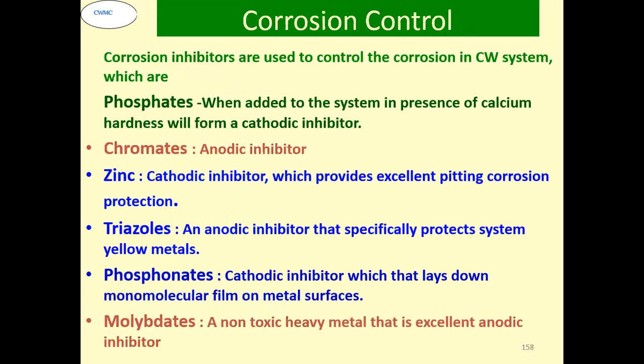Some of the important things are phosphates, chromates, zinc, triazole, phosphonates, molybdates. After that, chromates are generally ruled out these days because of the environmental considerations, and they are supposed to be toxic in nature, especially chromium 6+. Zinc is again a very good cathodic inhibitor, but it is also a heavy metal, so the restriction is it should not be more than 1 ppm in your water. Triazoles are generally used for the yellow metal, that means the brass, copper based systems.